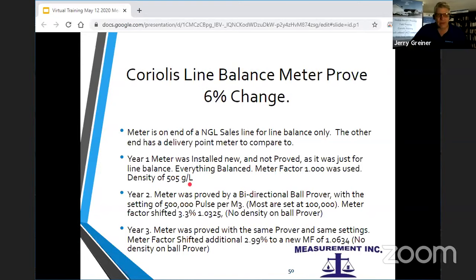The second year it was proved with a bidirectional ball prover. They used the settings of 500,000 pulses per cubic meter, which should have probably thrown up some red flags because just about always you'd use 100,000, not 500,000. But it worked fairly close. The meter factor had shifted about 3% after the first proof. There's no density, so we don't know what the density really was in that year.